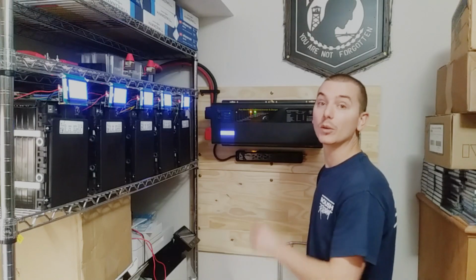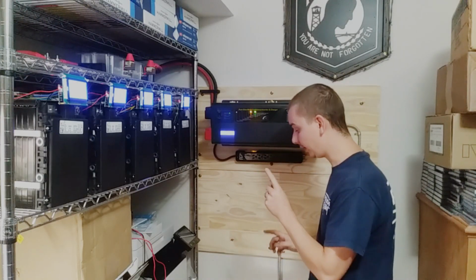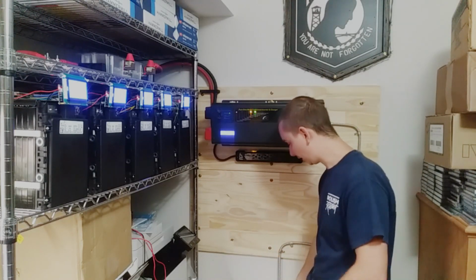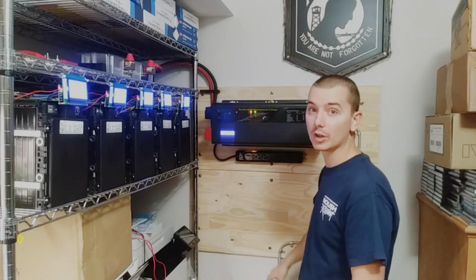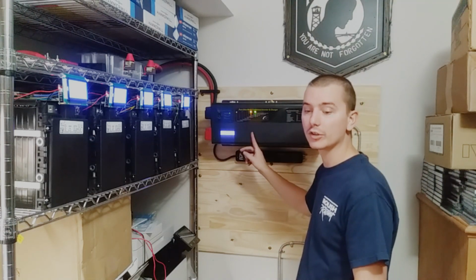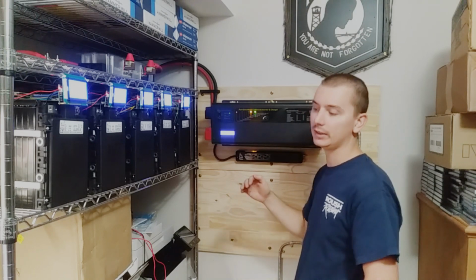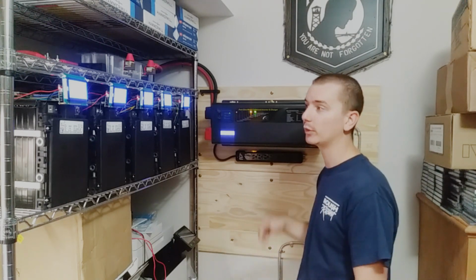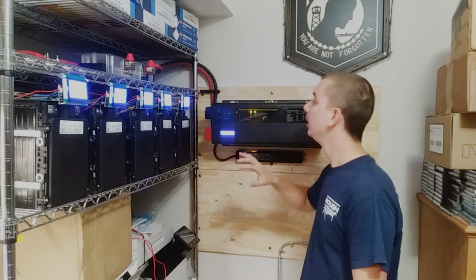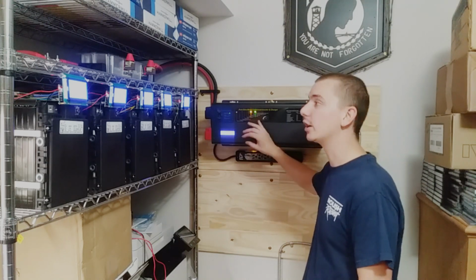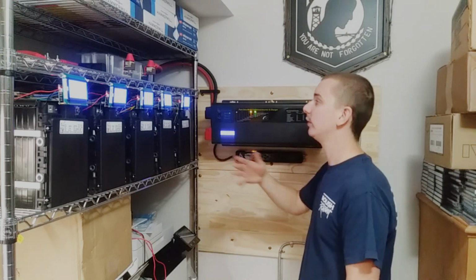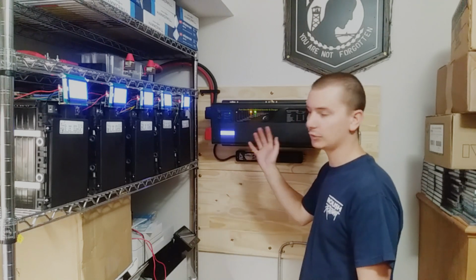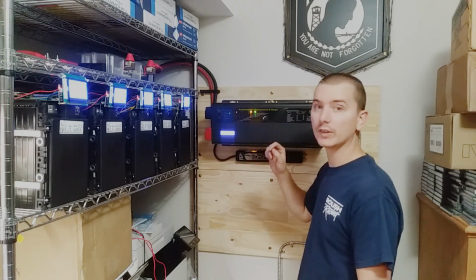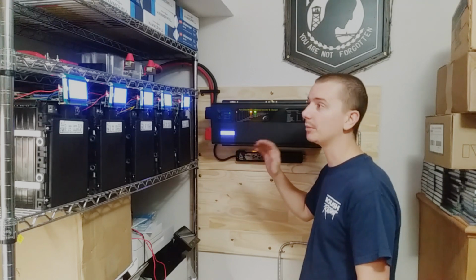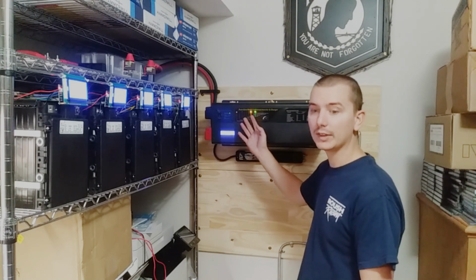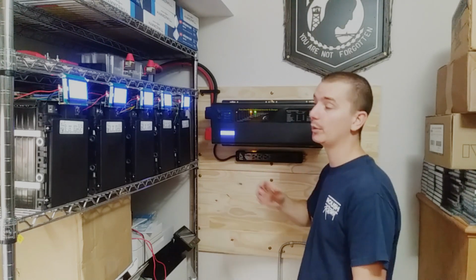That's not bad. So we just found our weak link, and it is the circuit that this outlet is on. It's a 15 amp circuit, and with this at 100% charge rate, the dehumidifier kicked on, and the surge load tripped the circuit breaker. So I reduced it back down to about 50% charge rate, which is fine for right now as general charging. In an emergency, if this were being charged off a generator, this would be turned to 100% and that dehumidifier would be unplugged so we wouldn't be using it.